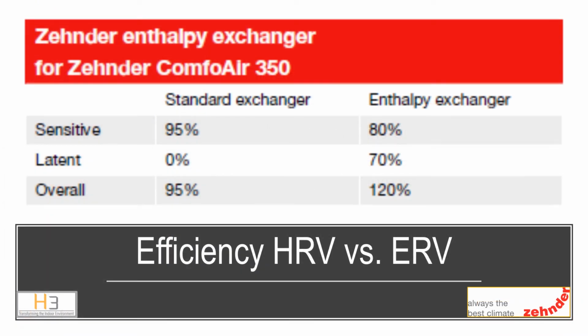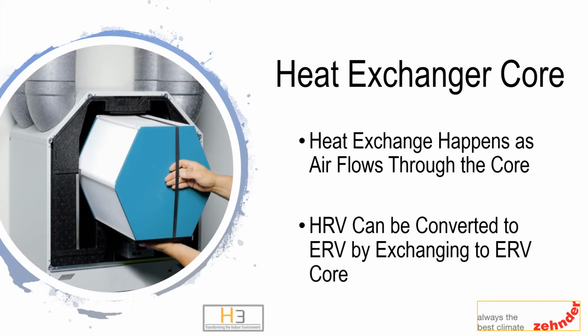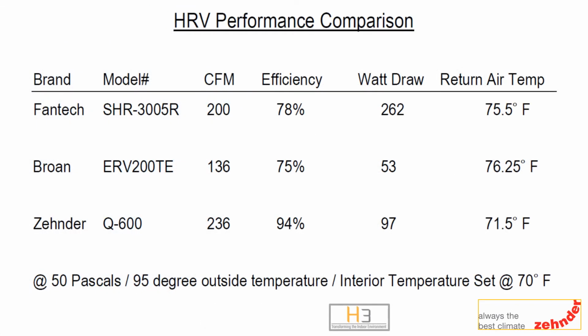This slide shows the comparison between a standard HRV core and the ERV core when it comes to overall efficiency. The use of the ERV is becoming more prevalent as moderating humidity levels within the home also enhances occupant comfort and health. Since the ERV redistributes condensate, no condensate drain is required. To review, heat exchange happens in the core. Zehnder units are designed with interchangeable cores so that an HRV can be upgraded to an ERV simply by changing the core. The cores are also easily removable for cleaning and maintenance.